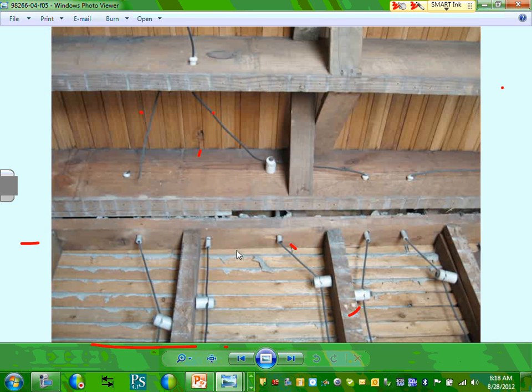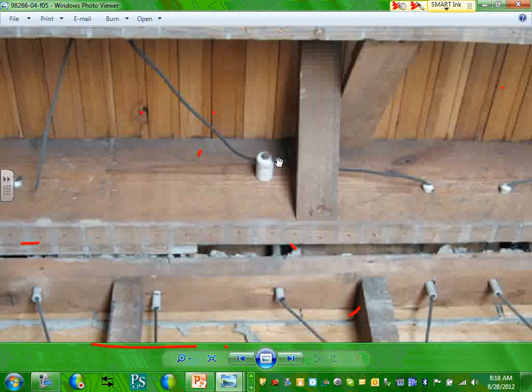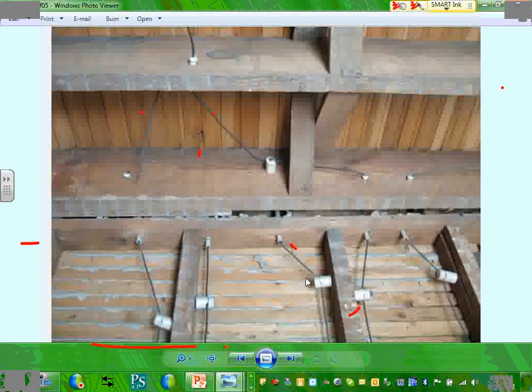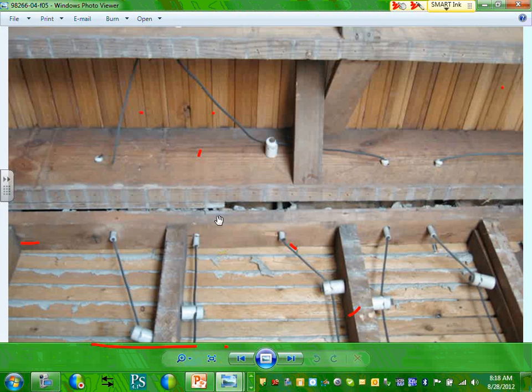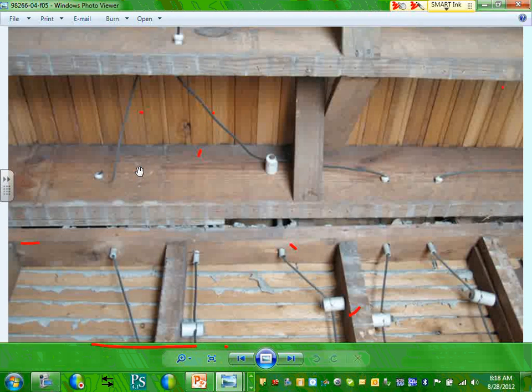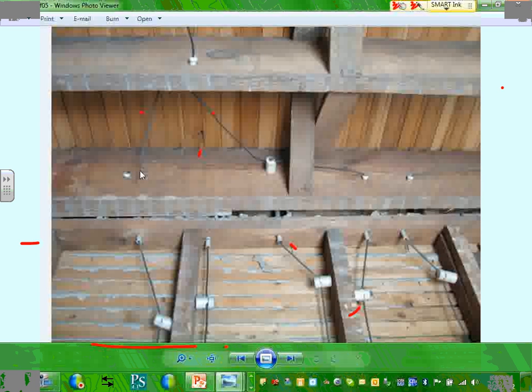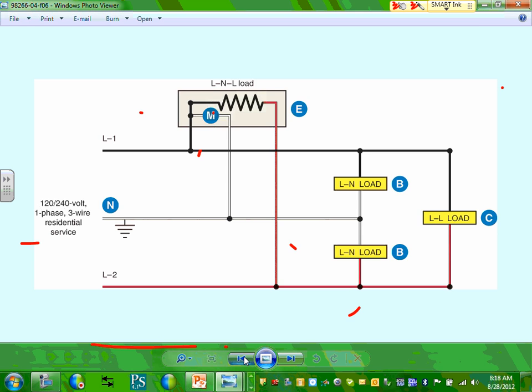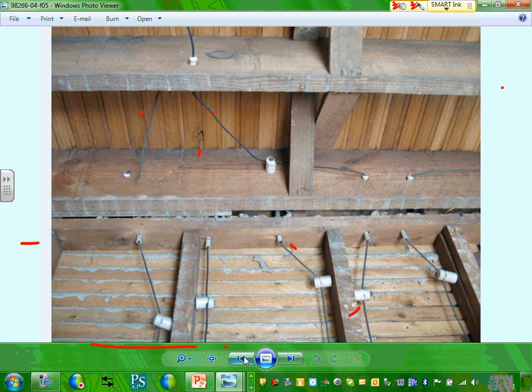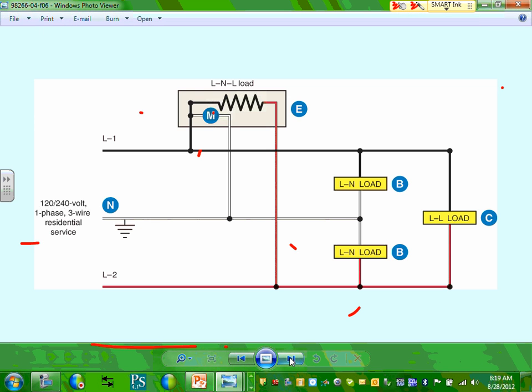Yeah, they're uninsulated cables and there's bored holes, the lighting insulators. So it's just bare cable that's hot running through the joints, with hopefully insulators. Yeah, and you can see that they're running them far away from each other. You can go the phase in one and the neutral in another one. So if you're to tab from these, if you open the walls, you have to remove them. If you tab from them, you have to put a J box. But again, you guys will rarely do that one.